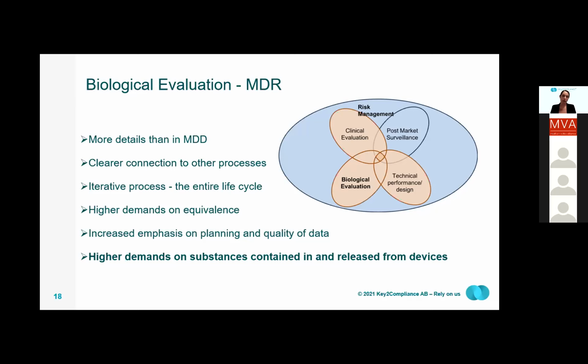So the MDR is much more clear on how the biological evaluation relates to other processes. It stresses that it's an iterative process. So for your device, you must consider the biological safety for the entire life cycle. There are higher demands on equivalence, and there's an increased emphasis on planning and quality of data. And for today, I will focus on the higher demands on substances contained in and released from your device. And that is, of course, also reflected in the documents that you need to have in your technical documentation for the device.